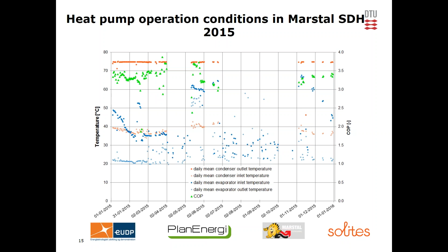For the evaporator side, that's also from the heat storage side. The inlet temperature is sometimes 50, 30, or even up to 60 degrees Celsius, while the temperature back to the pit storage is around 20 to 30 degrees. The annual COP is around 3.0 to 3.5 on average.